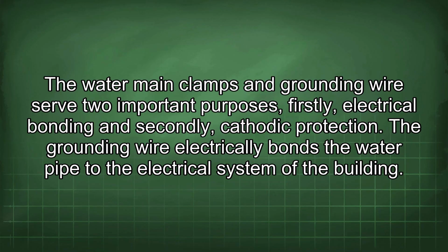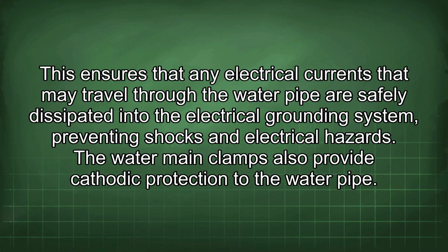Water main clamps and grounding wire serve two important purposes. Firstly, electrical bonding, and secondly, cathodic protection. The grounding wire electrically bonds the water pipe to the electrical system of the building. This ensures that any electrical currents that may travel through the water pipe are safely dissipated into the electrical grounding system, preventing shocks and electrical hazards.